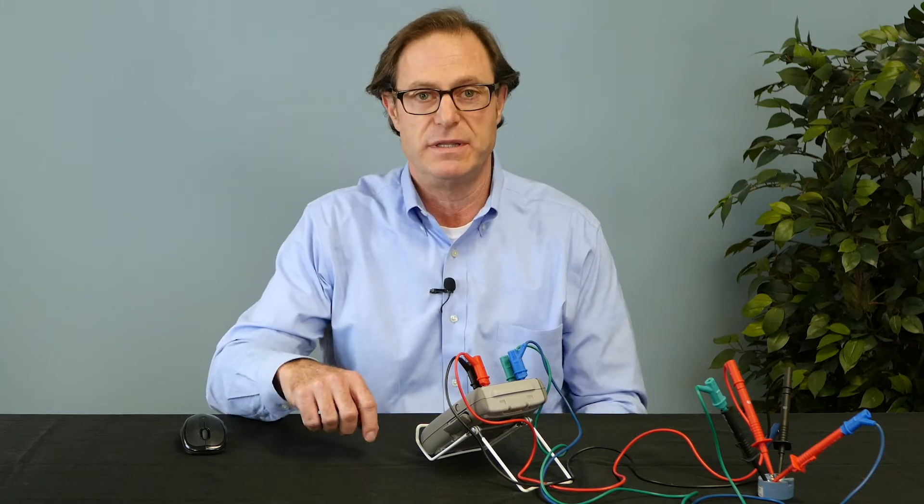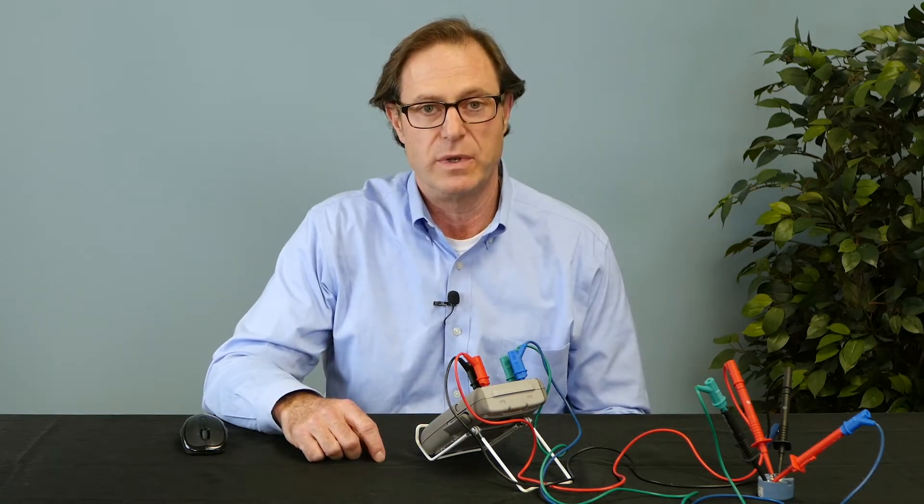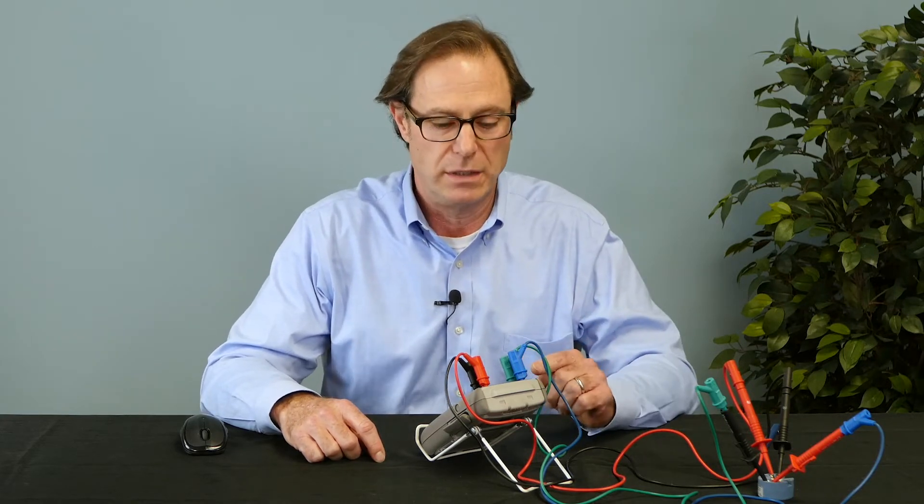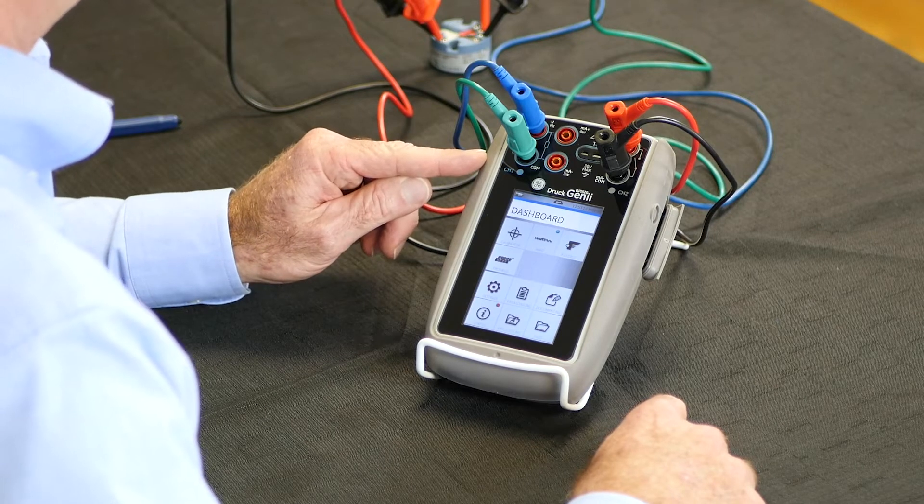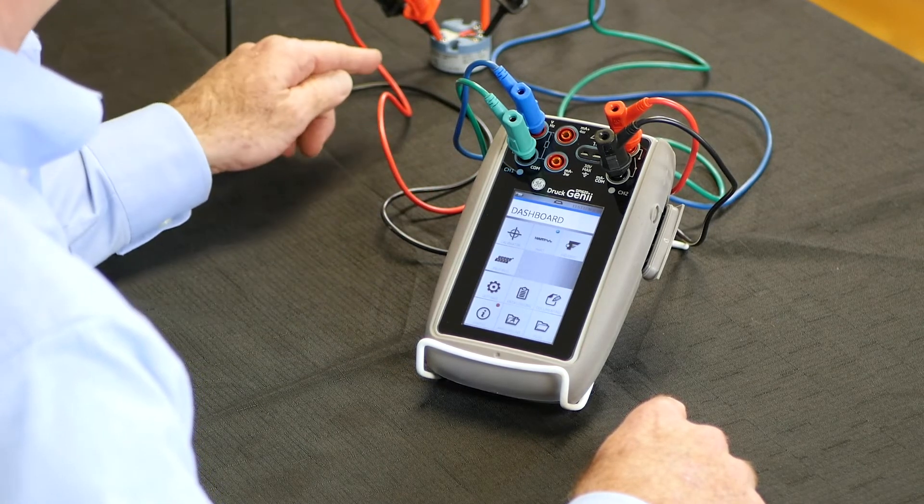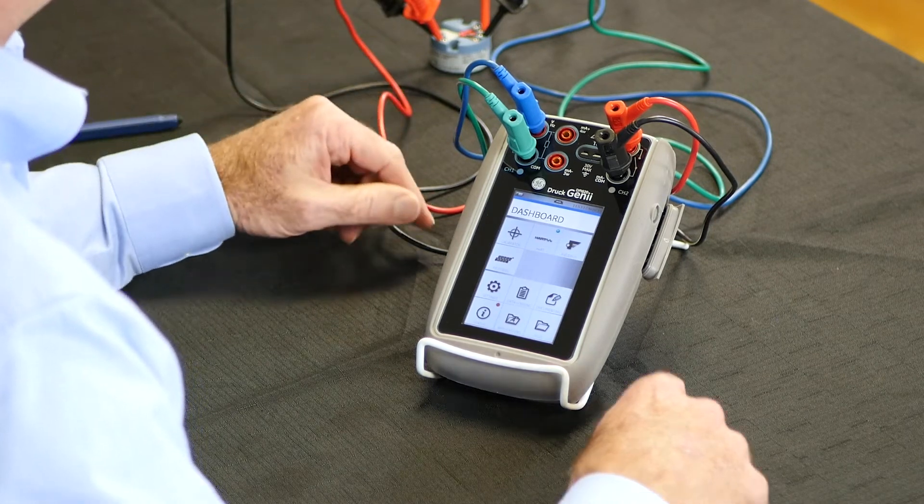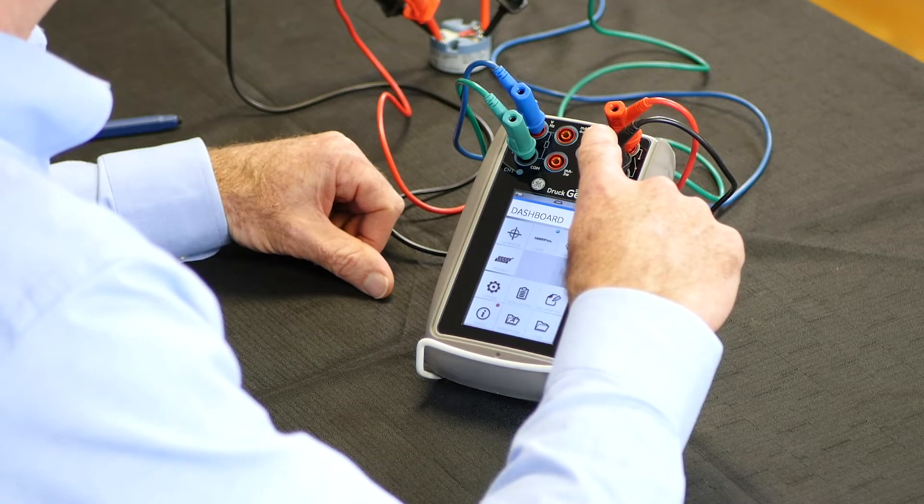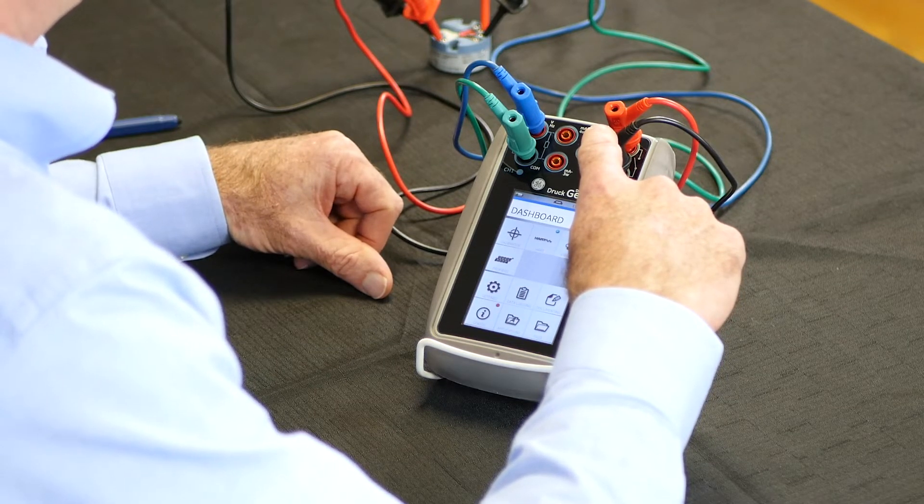To demonstrate the HART communicator, we have a temperature transmitter connected to the DPI 620. On channel one, we're simulating a zero to 100 degrees C RTD signal to the transmitter. And on channel two, we're providing a 24 volt excitation and measuring the four to 20 milliamp output off of the transmitter.